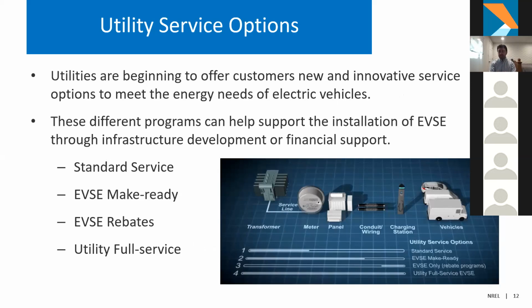And then bringing this all together, this is sometimes rather burdensome for some people. So in addition to the opportunity to upgrade all of this equipment or install your own EVSE, many utility companies are actually offering different service options. You might be most familiar with distribution equipment coming in from a transformer and going to the service meter or the utility meter, and then the facility owning the panel, conduit wiring, and charging station. As you can see here, there are a bunch of different options where, for some EVSE make-ready services, the utility owns the meter panel and conduit wiring, and a facility is only on the hook to install and own a charging station.